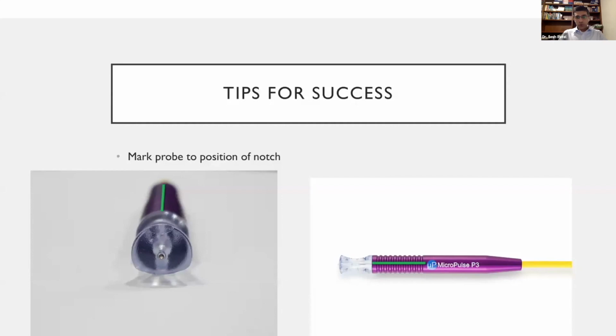So what I do is I get some Micropore tape and stick it over the probe in this area here, and then I use a marker pen to mark a line to indicate where the notch is. So you can see here that I've marked in green where the notch is. That's really helpful in terms of knowing where the notch is at all times. So that's one thing that I would recommend that people do. That way you ensure that you know where that notch is at all times.